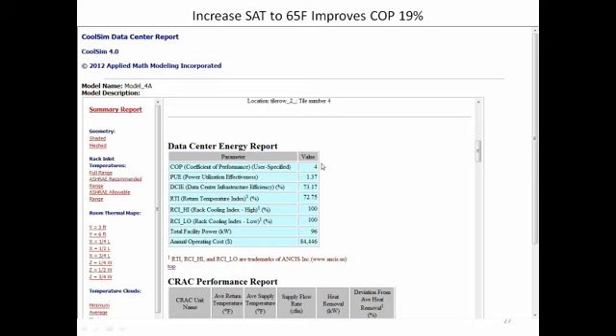Now I currently, Liz, don't have this set up as an N+1 room. I've only got one CRAC sitting there on. But what that icon control allows you to do is to network the two units together so that if a CRAC goes down, the other one will come up. And what you can do...